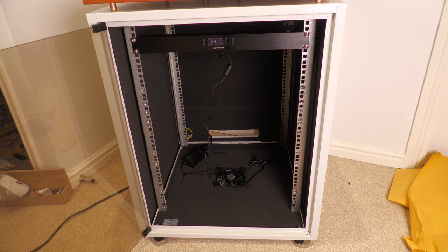So on, say, a very hot day when the servers are working really hard for some reason, if the rack started to get a little bit too hot, the fans can ramp up really easily to a very high speed and really quickly clear that heat out of the rack. So that's quite good. So what I'll do very quickly is go in a bit closer and take a quick look at the interface on this and show how it works, just because I know most people won't care about it, but if you're buying one of these, this could be quite useful. And then we'll do what everyone's probably wanting to see and get all the equipment installed back in the rack and see how well it all performs.